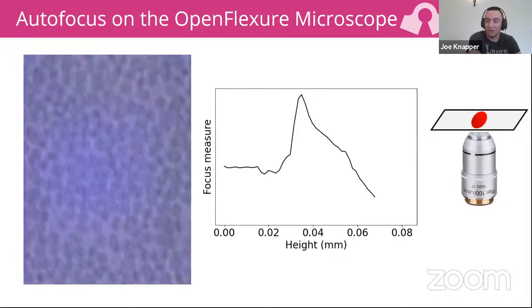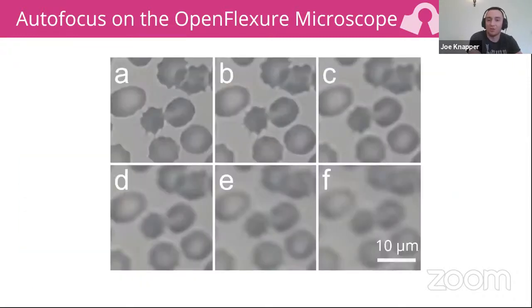But when attempting to diagnose malaria, you need the highest level of precision possible. The autofocus will reliably get to within around 3 microns. To give an idea of scale, here are some blood images taken on the microscope using 100x objective at the focal plane, and then 1, 2, 3, 5, and 10 microns away from the focal plane. Clearly we're aiming to be within 1 micron of the focal plane, and at this level of defocus, we'd be taking information away from the diagnostician.